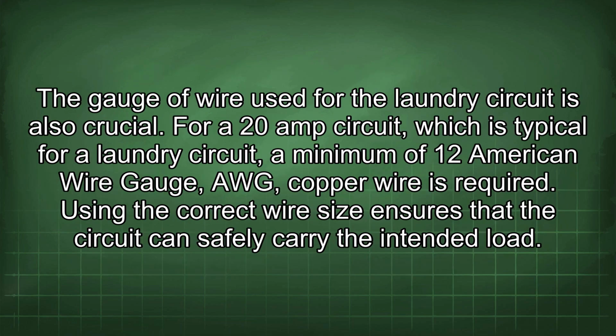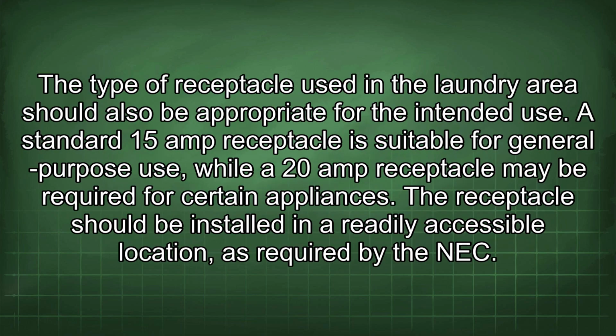The gauge of wire used for the laundry circuit is also crucial. For a 20-amp circuit, which is typical for a laundry circuit, a minimum of 12 American wire gauge (AWG) copper wire is required. Using the correct wire size ensures that the circuit can safely carry the intended load. The type of receptacle used in the laundry area should also be appropriate for the intended use. A standard 15-amp receptacle is suitable for general-purpose use, while a 20-amp receptacle may be required for certain appliances. The receptacle should be installed in a readily accessible location as required by the NEC.